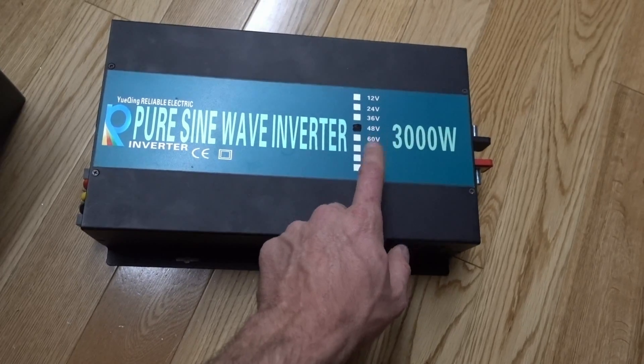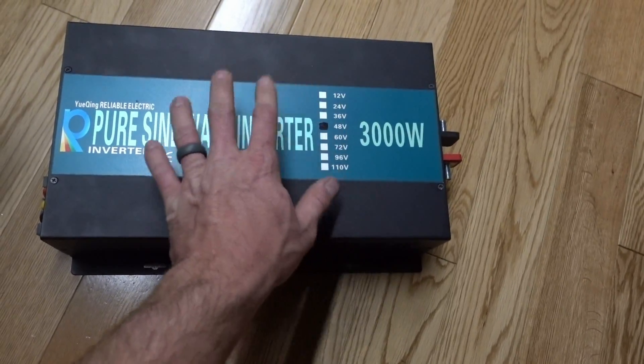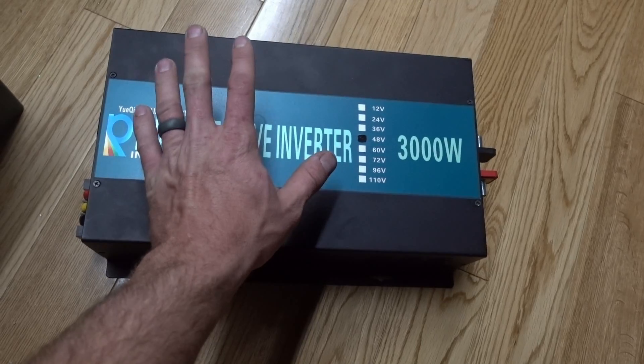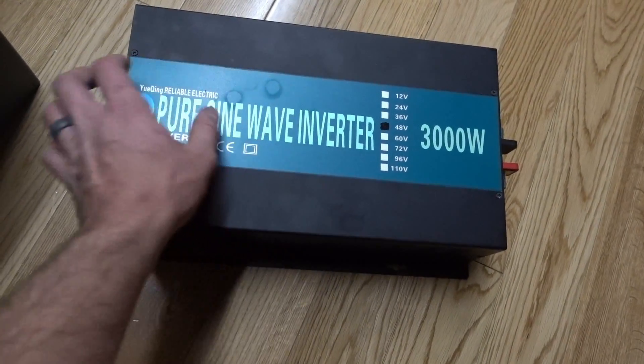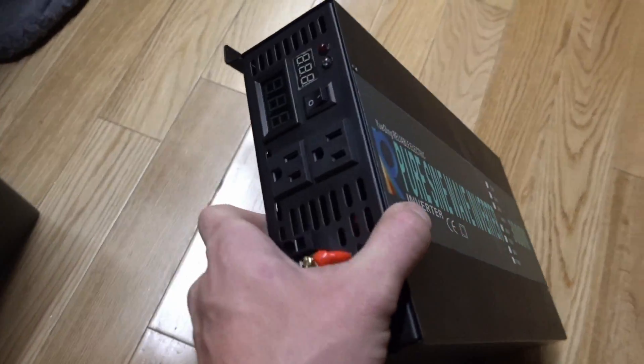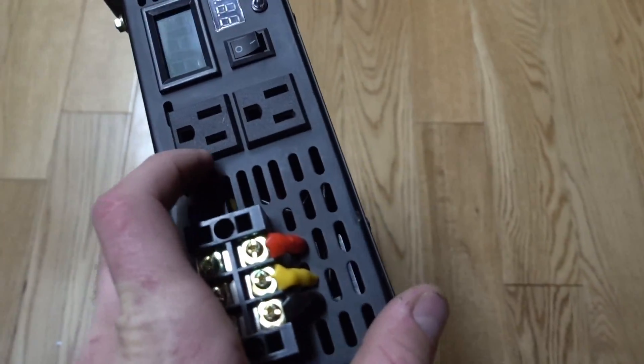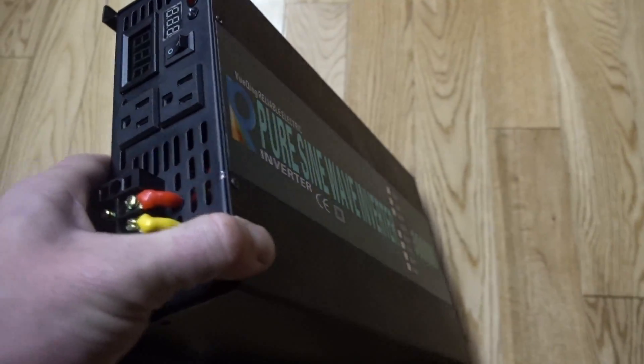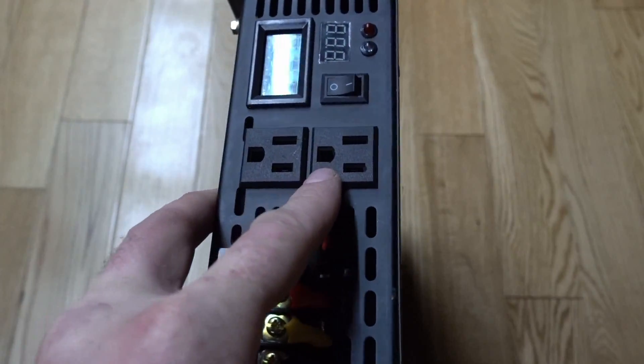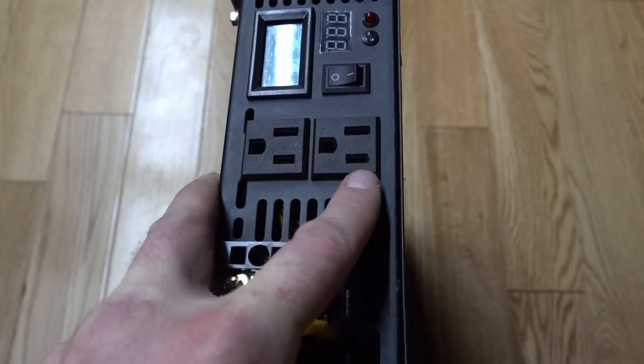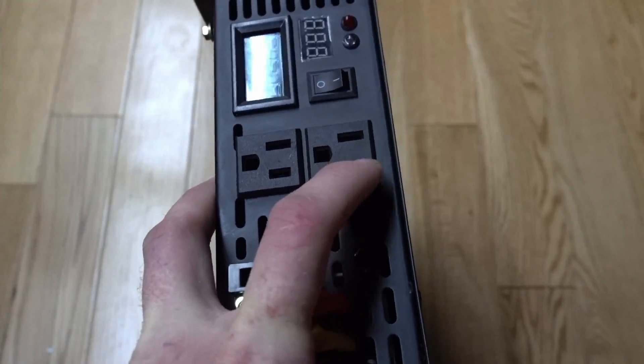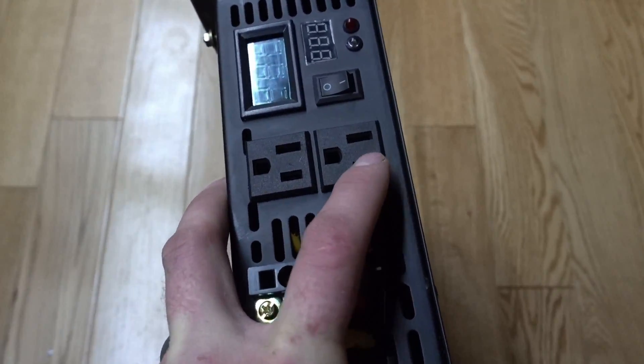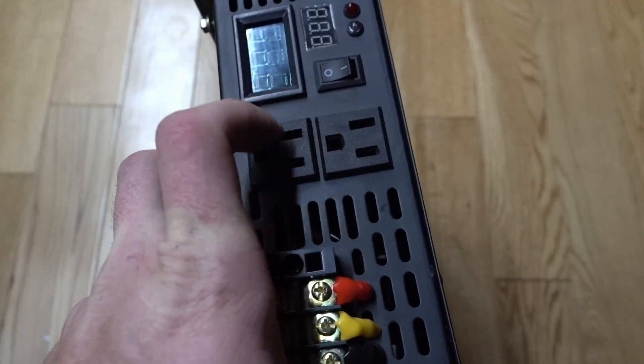We figured out that he accidentally shorted it by trying to hook it up to his house. What happens is these inverters have a semi-live ground, so these inverters do not have a neutral, or at least not the neutral that everybody's used to. This is alive, that's alive, and this ground is a partial live.